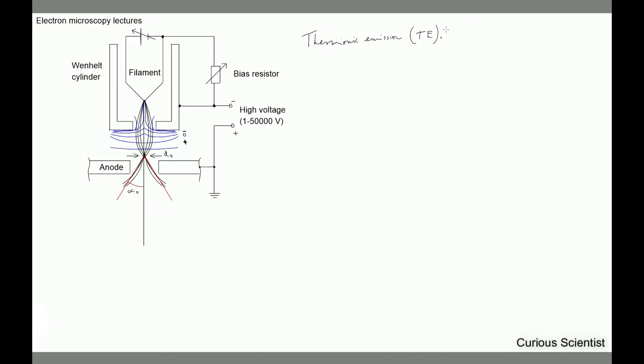What happens in the gun is that we run current through the filament, which makes it hot — really hot. Due to this temperature rise, the electrons become energetic enough to overcome the work function, which is basically the energy needed for electrons to leave the surface of the material. Once these electrons escape, we use an electrostatic field which pulls the electrons from the vicinity of the filament surface, accelerates them, and interacts with them in many different ways.